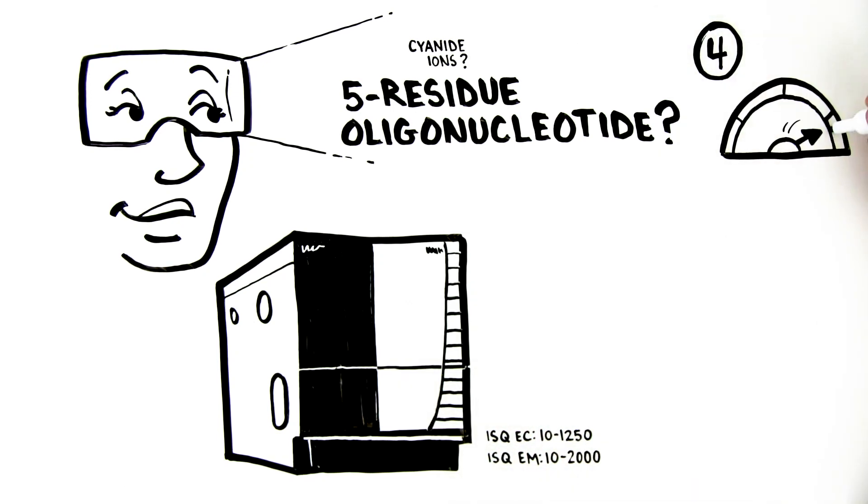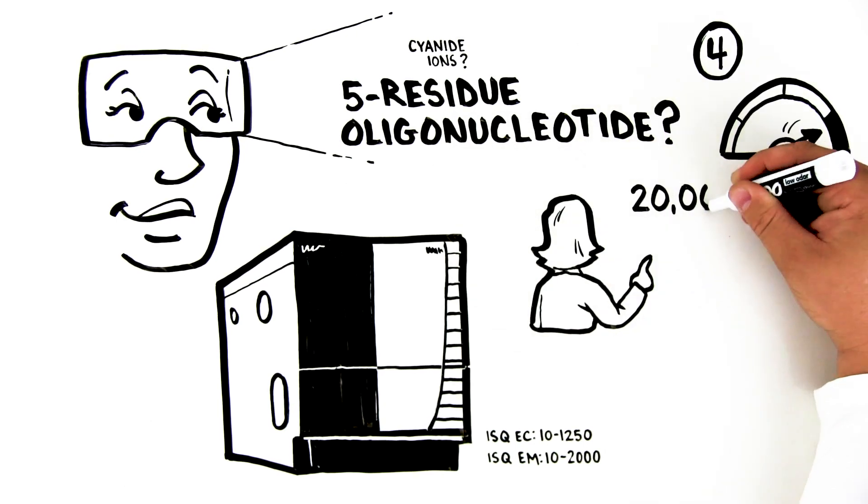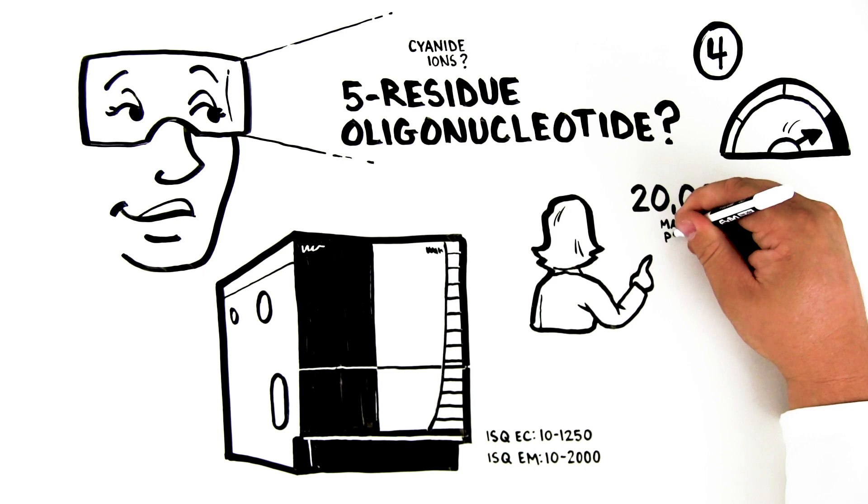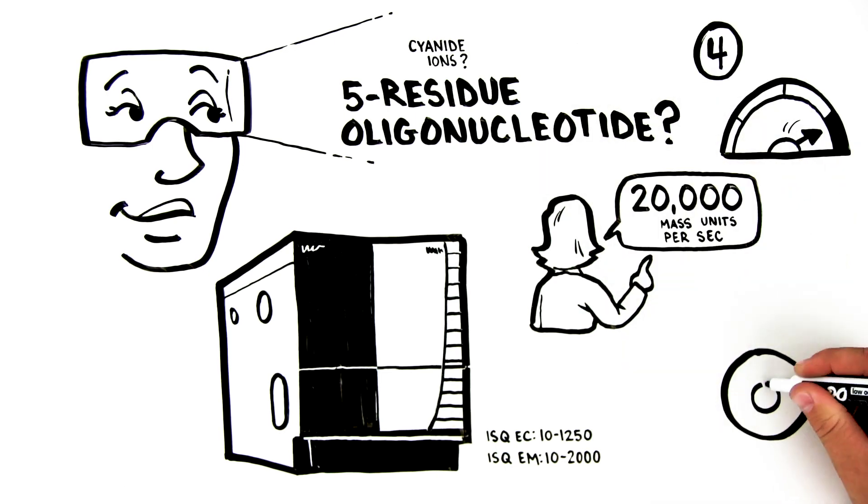Fourth, there's scan speed. In order to characterize a UHPLC separated peak properly, Jenny wants 20,000 mass units per second. A slower scan speed will mean she may not be able to get accurate quantification.